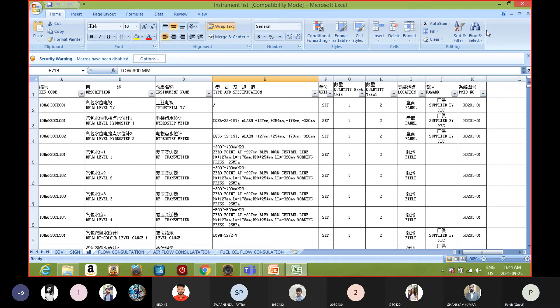After P&ID, we have an instrument list. So from the P&ID, we decide how many instruments we require, and these are the list of instruments and type of instrument. After the list is prepared, we decide how many analog inputs, how many analog outputs, how many digital inputs, and how many digital outputs are required for our control system. And accordingly, based on input and output, we decide how many controllers we require and how many panels we require. These are discussed during the engineering phase.